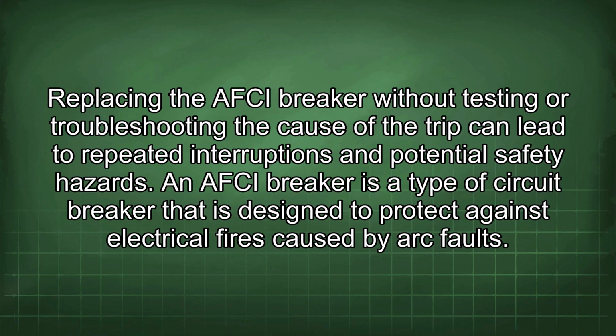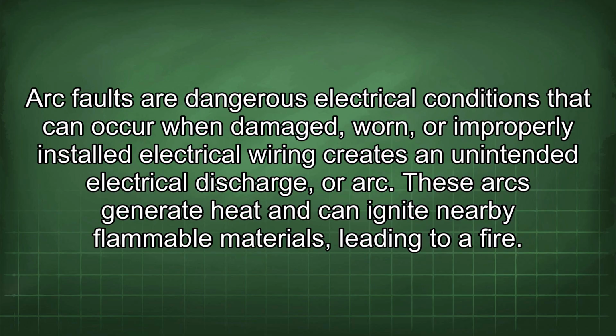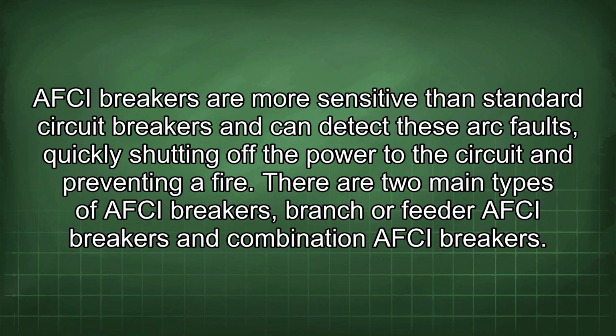Replacing the AFCI breaker without testing or troubleshooting the cause of the trip can lead to repeated interruptions and potential safety hazards. An AFCI breaker is a type of circuit breaker that is designed to protect against electrical fires caused by arc faults. Arc faults are dangerous electrical conditions that can occur when damaged, worn, or improperly installed electrical wiring creates an unintended electrical discharge, or arc. These arcs generate heat and can ignite nearby flammable materials, leading to a fire. AFCI breakers are more sensitive than standard circuit breakers and can detect these arc faults, quickly shutting off the power to the circuit and preventing a fire.